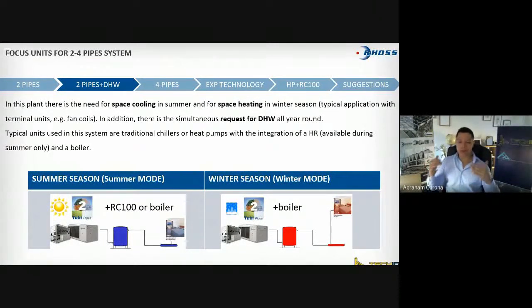Look at, I know when I'm producing chilled water or when I'm producing heat pump, I project some of that heat into the environment. So in one way or another, you're wasting free energy. So I'm thinking I may have a scenario, it could be a hotel where you are probably trying to have an air conditioning system during summer and winter, but you want to have a domestic one, right? So you say I can put a heat recovery in the chill water of the chiller, or even in the heat pump, and I'm going to start to recover maybe temperature between 45 to 55, and I'm going to use that hot water to my domestic water or to any other heating water design that I have inside the building. So first thing, is this system now called a 4-pipe?